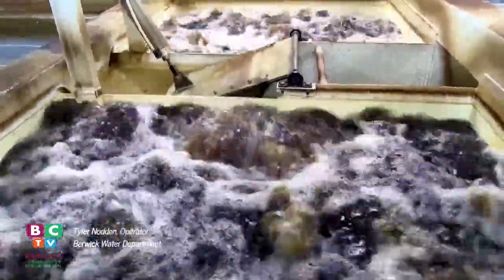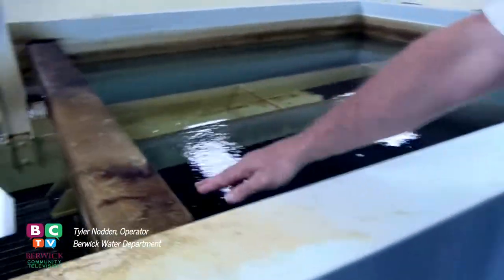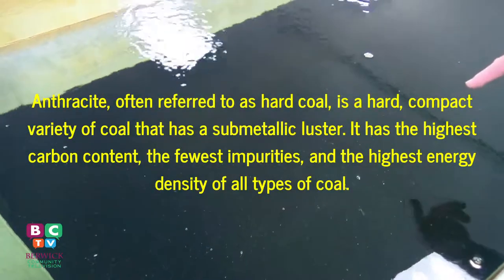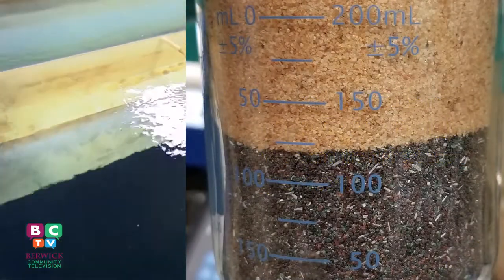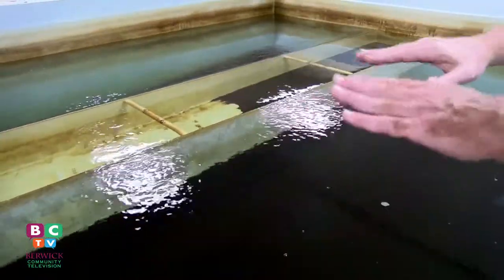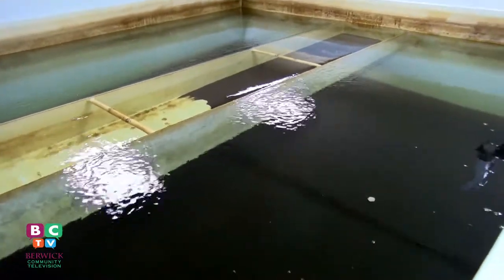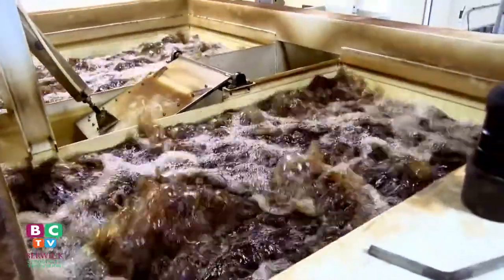Once that clears, the treatment starts over. The water comes in here, comes up here, and moves over here. Looking at this other filter — it's going down through probably four or five feet of media. That's anthracite on top, then sand on the bottom, and some garnet. Everything trapped here gets pushed down through there and gets trapped by the sand, anthracite, and garnet. You can obviously see how dark that is, and we get rid of that and don't put it in our system.